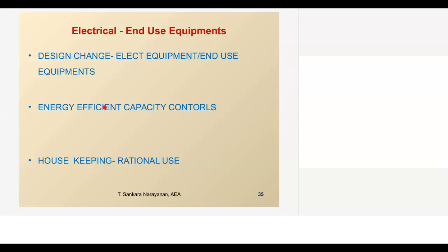The second one is that we have to review the energy efficient capacity control. What is the present capacity control? Like we always say, go for a damper survey and a valve survey. Wherever control valve and damper operation is there, one has to see what the energy efficient capacity control will be. Then housekeeping and rational use, this is a management requirement.